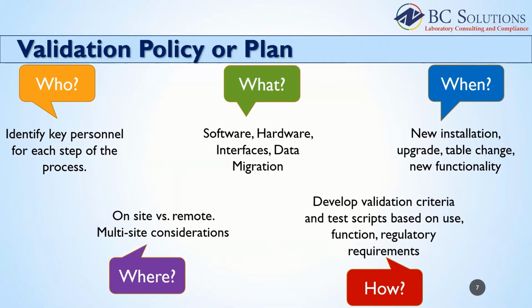Where is your validation being performed? Can portions of your validation be performed remotely? Are you a multi-site? Do some test scripts need to be performed at multiple sites due to different configurations or procedures? Each facility will be responsible for their own PQ, or validation of their people and processes.